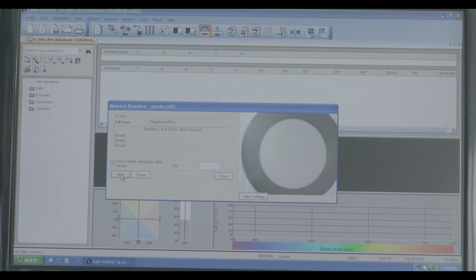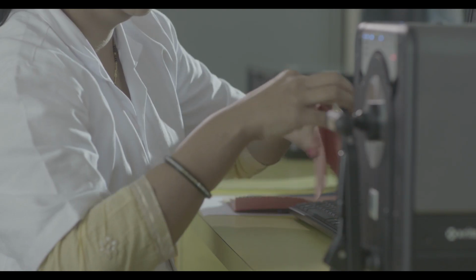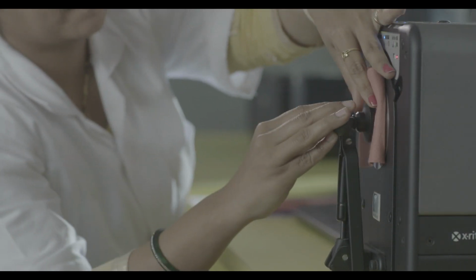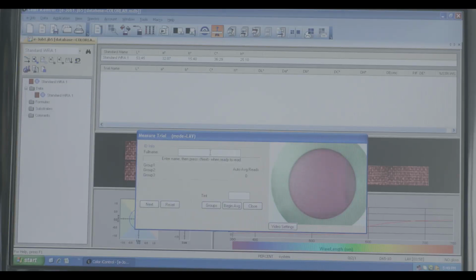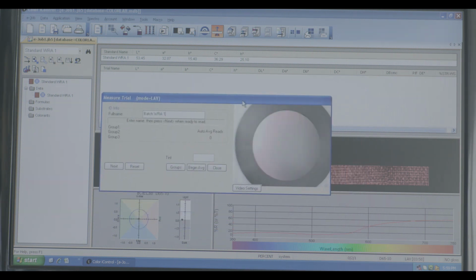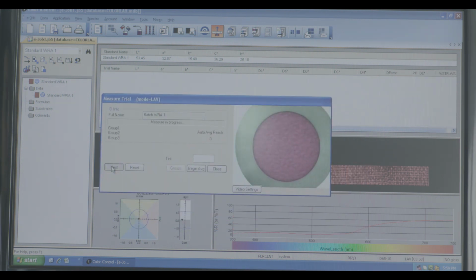Name the standards and follow the software instructions for loading the sample at the viewport. We are taking 4 measurements per sample at different areas of the sample. The number of measurements per sample can be changed as per the requirement. After standard measurement, the batch sample needs to be measured. Select Measure Trial. Name the batch sample and follow the same procedure as that of standard measurement. We can measure multiple batch samples against one sample.